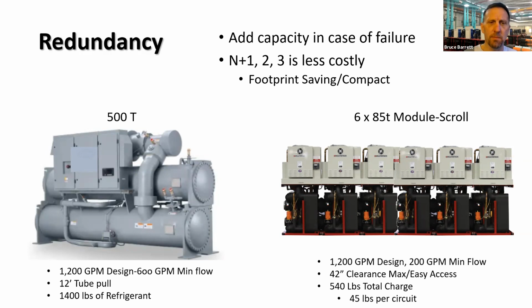Also, that 500-ton machine turn down. If it could turn down to 10, 15%, say it has a variable frequency drive on it, that might be 150, 200 tons minimum turn down. On a modular chiller, you're able to turn down to your smallest compressor size. So 6 85-ton modules, it's about a 40-ish ton capacity. We can turn down to 20 tons of capacity, so tremendous turn down.